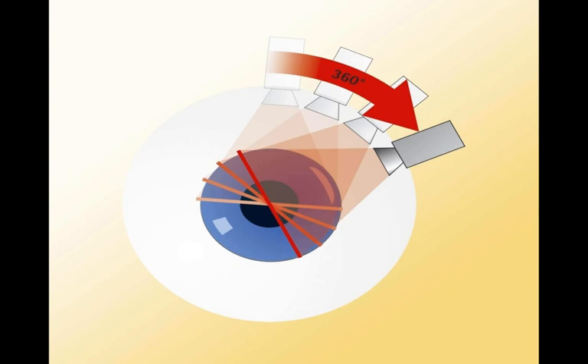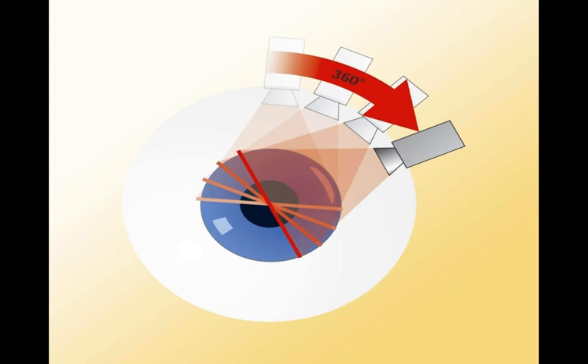With this device, the slit projection shows us that the camera sweeps through a total of 180 degrees, allowing us to get 25 or 50 cross-sections of the eye. The biggest advantage over what we had in the past—such as with the OrbScan, which is the first generation—is that it allows us to take the thinnest part of each slice, put it back together, and create a three-dimensional picture. With older devices, if you did a horizontal slice, you can't put it back together because you have no reference point. So you don't end up with a very accurate three-dimensional image.